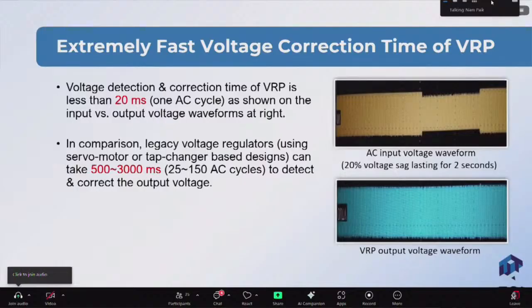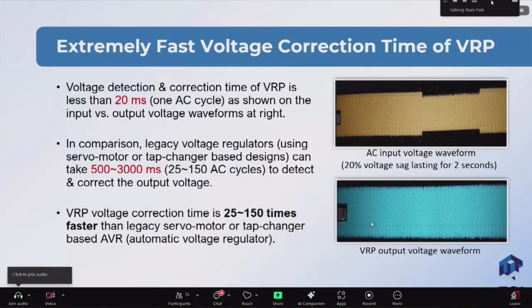In comparison, legacy voltage regulators using servo motor or tap change technology can take half a second to 3 seconds, which is 25 to 150 AC cycles, to detect and correct the output voltage. I'll show a video comparing them side by side. Our voltage correction speed is 25 to 150 times faster than the servo motor or tap changer. By the way, 99% or more of the voltage regulators found in Africa and Asia are one of these two types, servo motor or tap changer, because they're very low cost and built by millions every year in China and India, among other places.